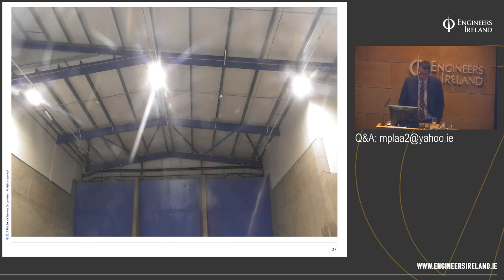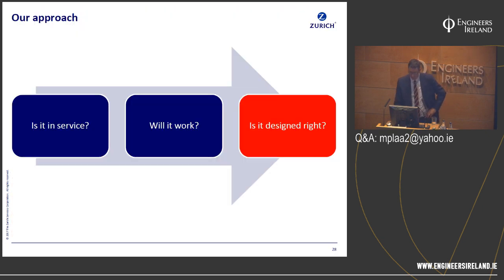This is a site. I'm sorry I can't show you the video on this one, but this is a deluge system where you've got triple IR flame detectors operating a solenoid valve, and this is on a waste to energy risk where we've got shredded wood biomass on a waste to energy plant where I did a full discharge test to make sure the system was fit for purpose. And it was a good example of actually proving that system delivering water for at least 10 minutes to make sure the pumps, the spray pattern and the system operated as intended. So that's the will it work bit.